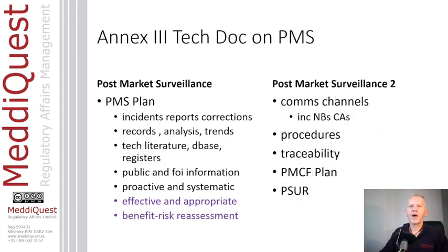Specifically, post-market surveillance is also now included, and the technical documentation from post-market surveillance is included in Annex 3. So remember to decide that this is part of your technical documentation for the device as well.